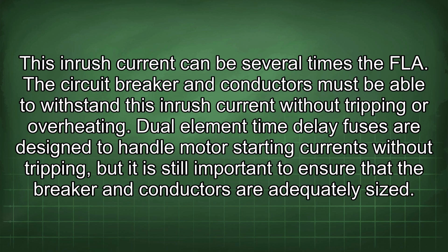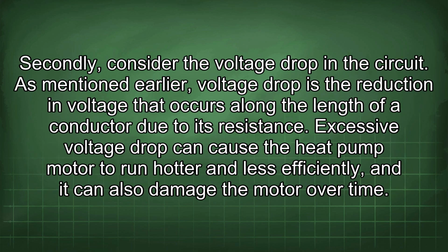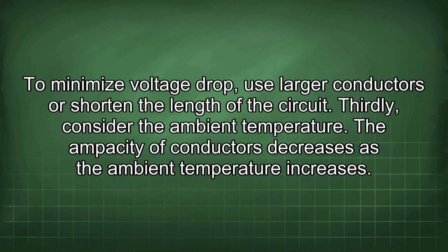Dual element time delay fuses are designed to handle motor starting currents without tripping, but it is still important to ensure that the breaker and conductors are adequately sized. Secondly, consider the voltage drop in the circuit. As mentioned earlier, voltage drop is the reduction in voltage that occurs along the length of a conductor due to its resistance. Excessive voltage drop can cause the heat pump motor to run hotter and less efficiently, and it can also damage the motor over time. To minimize voltage drop, use larger conductors or shorten the length of the circuit.